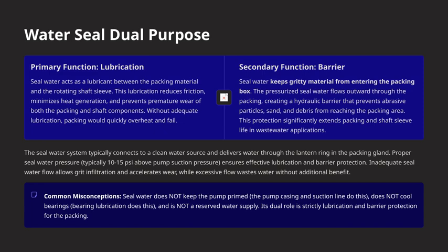Next, the secondary function of the seal water is to serve as a barrier. It keeps gritty materials, such as dirt, sand, and debris, from entering the packing box. The pressurized seal water flows outward through the packing, creating a hydraulic barrier. This barrier prevents abrasive particles from reaching the packing area, which significantly extends the life of both the packing and the shaft sleeve, especially important in wastewater applications where such contaminants are common.